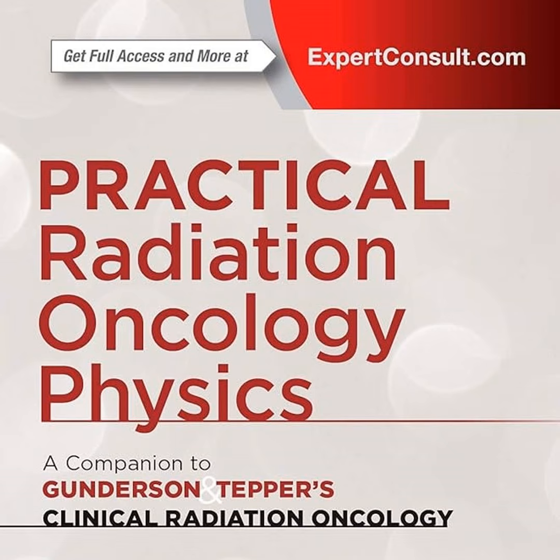Radiation bounces. Exactly right. The physicist's job is to meticulously model the out-of-field scatter. Radiation scatters inside the patient's body, and leakage radiation physically penetrates through the heavy shielding in the head of the linear accelerator. So they have to calculate all of that stray dose. Yes, they calculate exactly how much of that stray dose will travel down to the fetus. Then they design custom external shielding. I have seen physicists literally build physical bridges out of heavy lead blocks over the pregnant patient's abdomen on the treatment table. That is amazing.